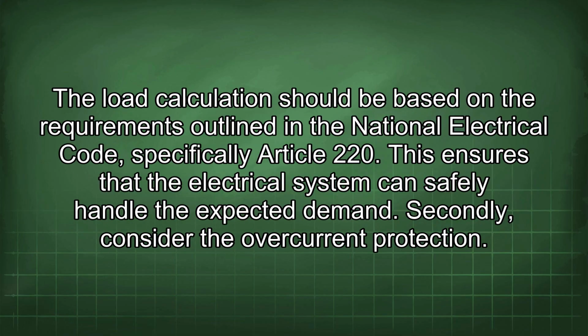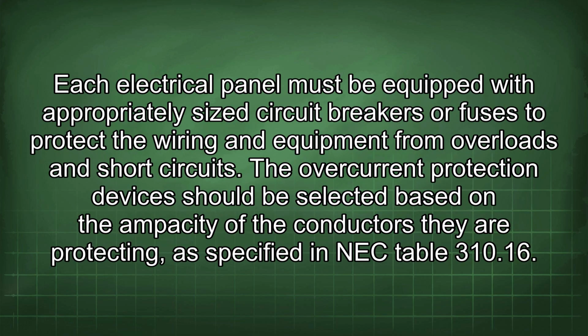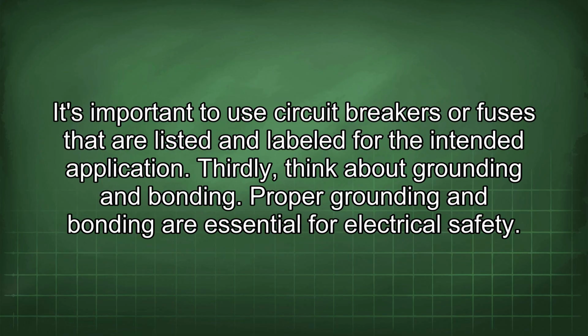The load calculation should be based on the requirements outlined in the National Electrical Code, specifically Article 220. This ensures that the electrical system can safely handle the expected demand. Secondly, consider the overcurrent protection. Each electrical panel must be equipped with appropriately sized circuit breakers or fuses to protect the wiring and equipment from overloads and short circuits. The overcurrent protection devices should be selected based on the ampacity of the conductors they are protecting, as specified in NEC Table 310.16. It's important to use circuit breakers or fuses that are listed and labeled for the intended application.